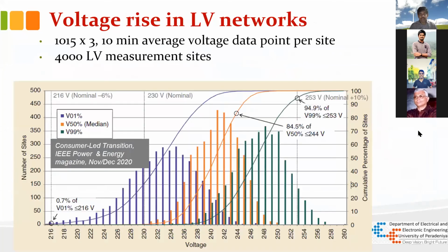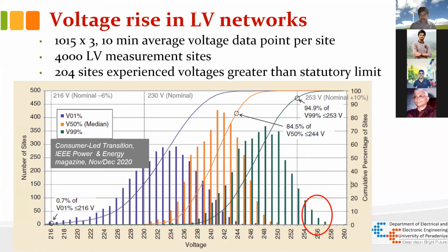This is again a similar graph, but shown in South Australia. This is 4,000 LV measurement sites in Queensland, with 1,015 measurements for three phases, taken as 10-minute average voltage. You can see that the 99th percentile voltage has gone up in around 204 sites, where the voltage is greater than the statutory limit. So this is a real problem for renewable integration.